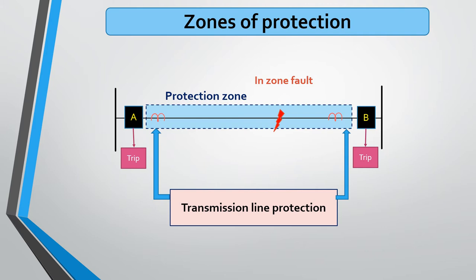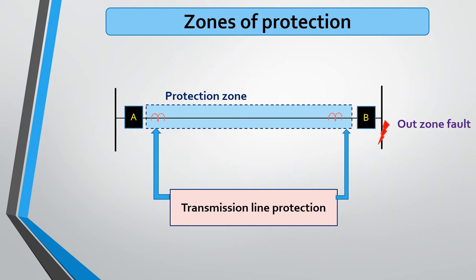This is the zone of protection for the transmission line. After clearing the fault, the circuit breaker will again get closed and work normally. In the second case, if a fault occurs on this particular bus bar, circuit breakers A and B are not going to give any protection. Fault current will flow through the entire system and may interrupt the complete power system — that is why zones of protection are important.